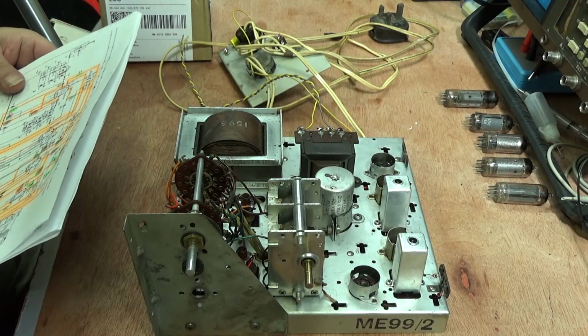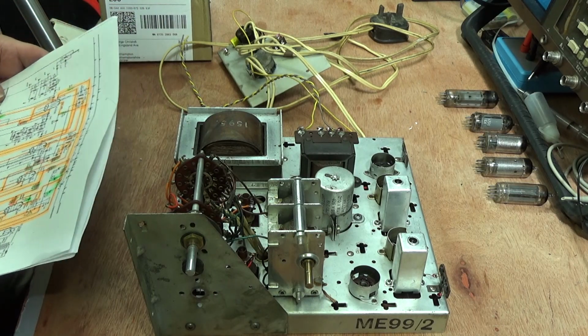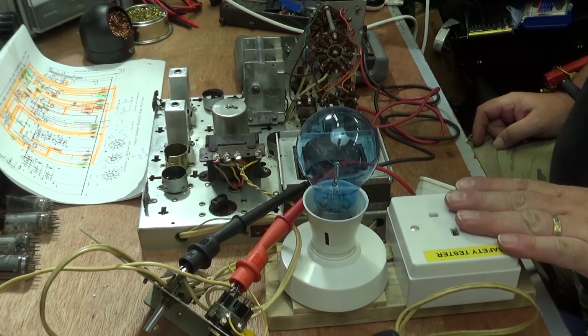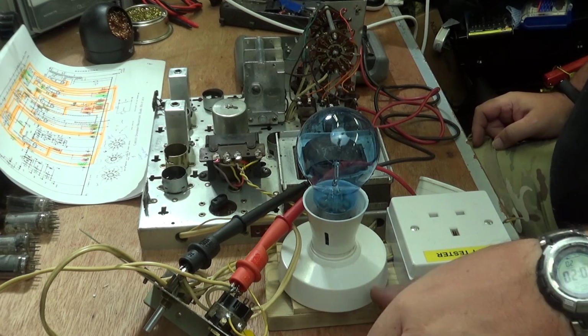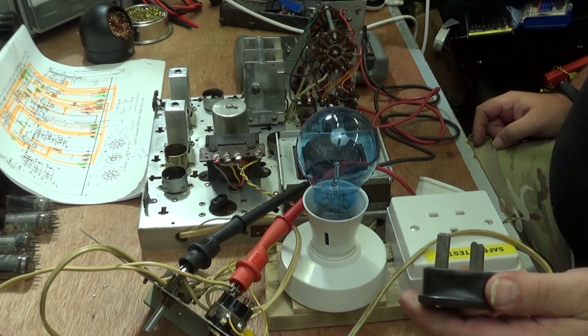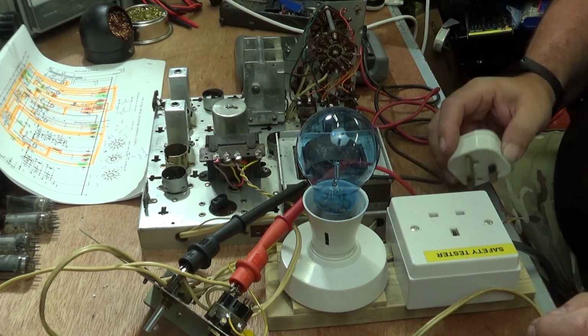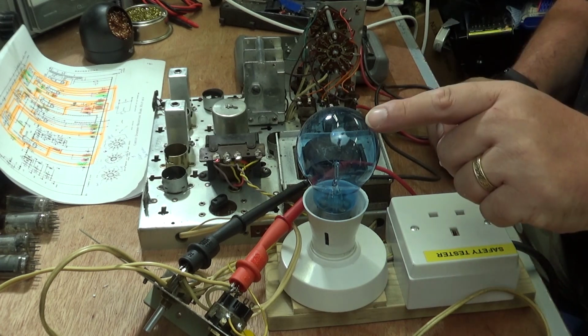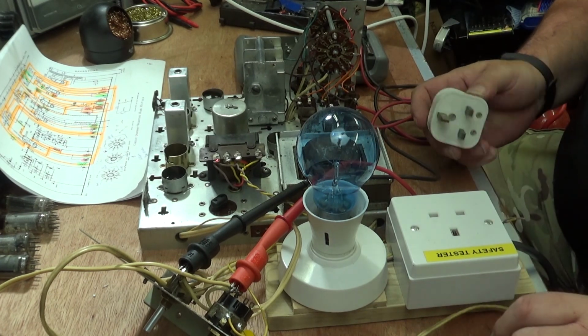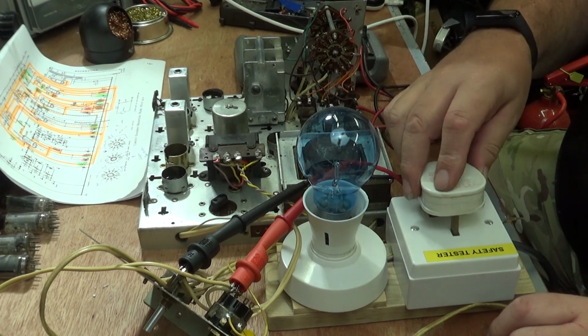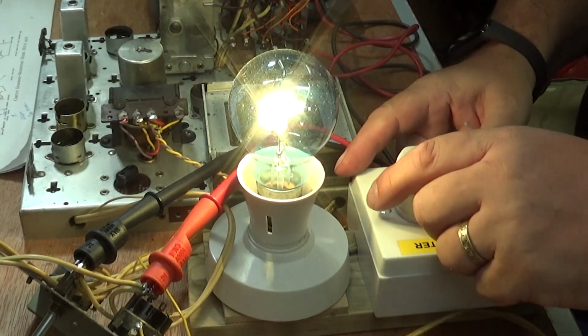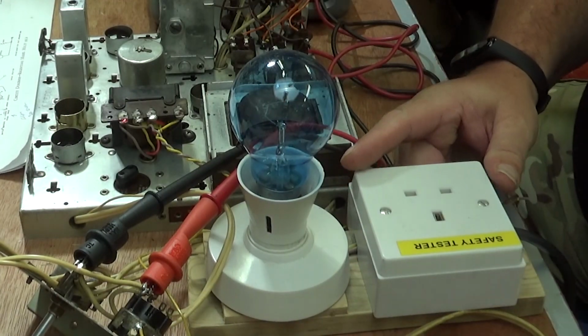So I think the thing to do is get the voltmeter and check to see what it does. We're all set up to do the first test, which is AC input. The isolation transformer is switched on, the safety tester is in place. Before I plug in the safety tester, I'm going to test it, because I don't know if this bulb is any good, so I'm going to put the shorting plug in. I now know the bulb is good, so I can turn that off.